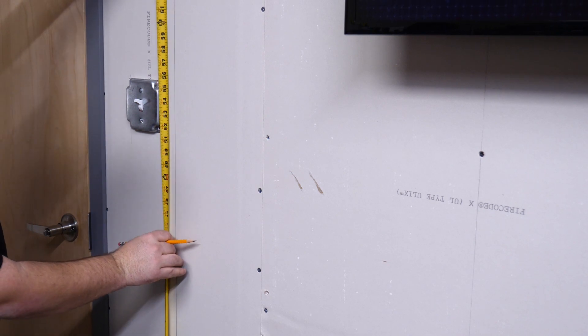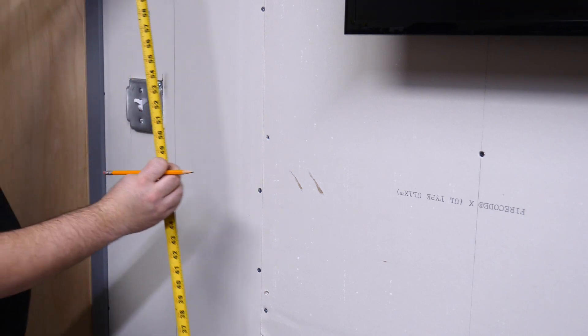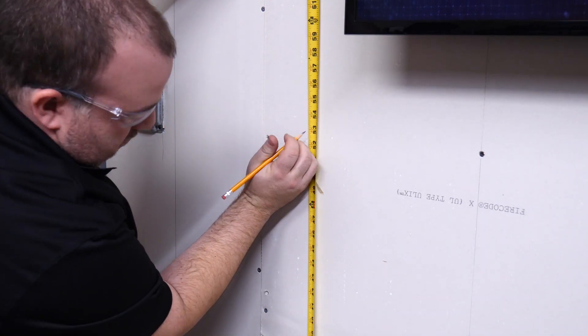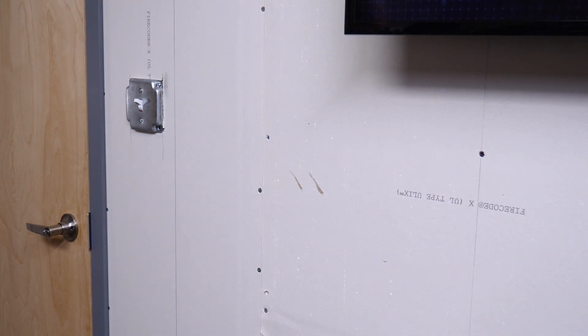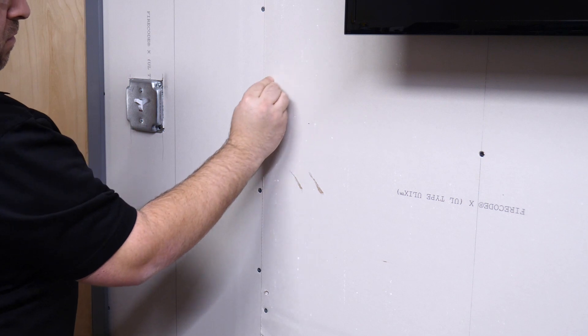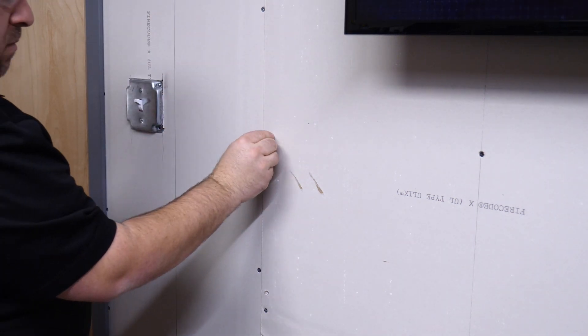The first step to installing one of these brackets is to make sure it matches any other electrical outlets or switches in the room you're working in. Typically, these are 18 inches off the floor for outlet height or 48 inches for switch height, but this can vary room to room, building to building.